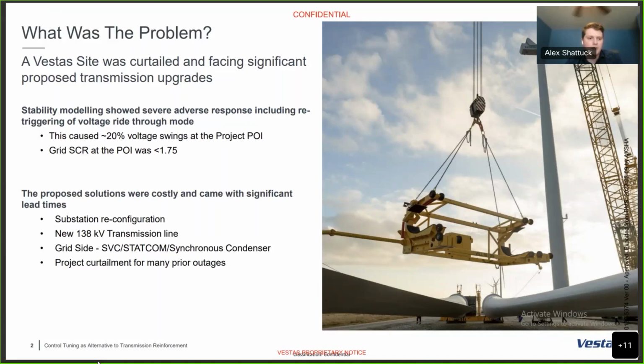Another solution was a new 138 kV line. What we saw was partly weak grid and partly a transmission stability constrained limit being hit, so the 138 line was another path for the megawatts and megavars to get out of that pocket. Then a grid-side SVC and STATCOM, or synchronous condenser, could help with the SCR. STATCOMs and SVCs would help push more VARs over that line and get it out.